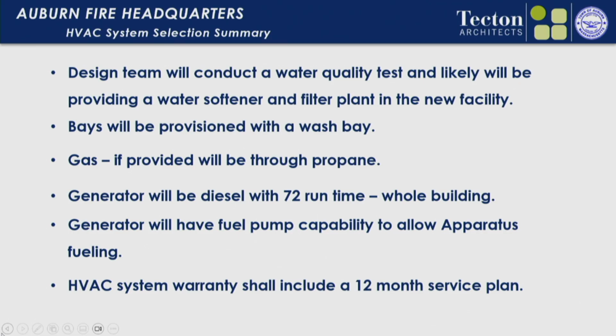Most of those tanks, and we've done this on a number of stations, are double walled, so they can be above ground, set up underneath as basically a bladder tank under the generator. The only thing you'll need to include is a fueling pad, a concrete pad the truck pulls onto with ribs in it so that any discharge or overspill hits the pad and is retained.